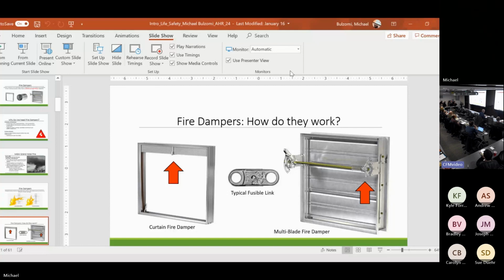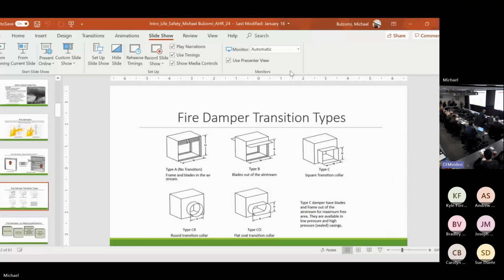Think if I had 3 of these together, 2 tall, all this middle stuff, it's all going to be in the airstream. Put whatever transition you want on it. It's never going to be 100% free area. It's negligible between a curtain fire damper and a multi-blade fire damper when they get very large.